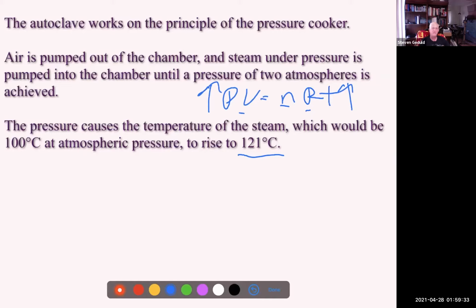So it can be a lot higher temperature, so I don't have to hold it quite as long at that temperature. Most autoclaves run around 15 to 20 minutes to sterilize a load of instruments, depending on the size and how much you put in. All the autoclaves are tested weekly, I think it's federal law actually. You throw a test strip in your autoclave, run it with your instruments once a week and send it to a government lab, and they check to make sure everything's dying in there.